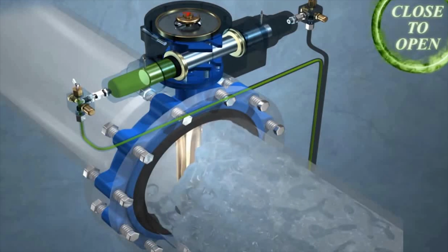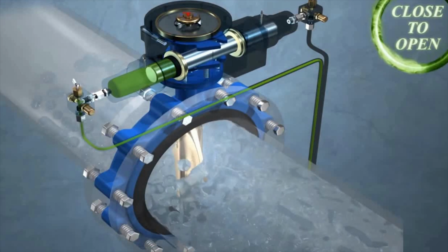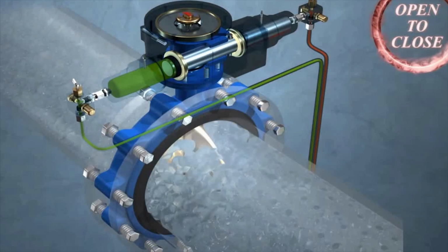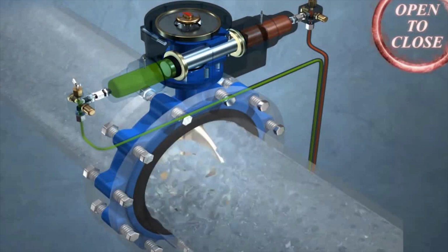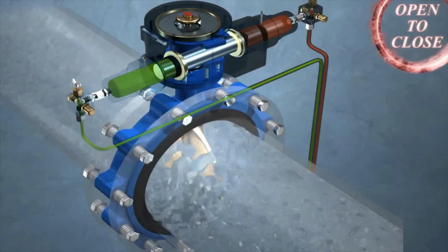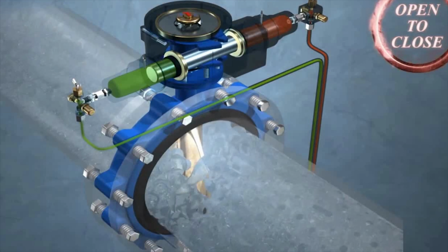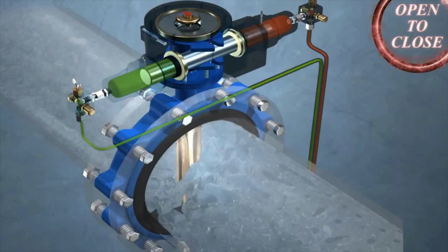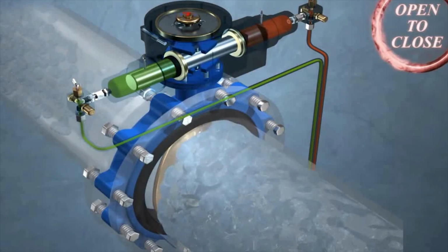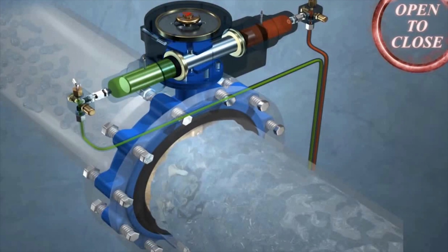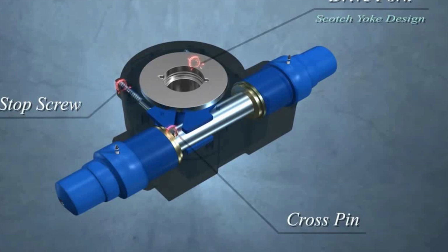The hydraulic cylinder consists of a hollow cylindrical tube along which a piston can slide. The term single-acting is used when the fluid pressure is applied to just one side of the piston. The piston can move in only one direction, a spring being frequently used to give the piston a return stroke. The term double-acting is used when pressure is applied on each side of the piston. Any difference in force between the two sides of the piston moves the piston to one side or the other.